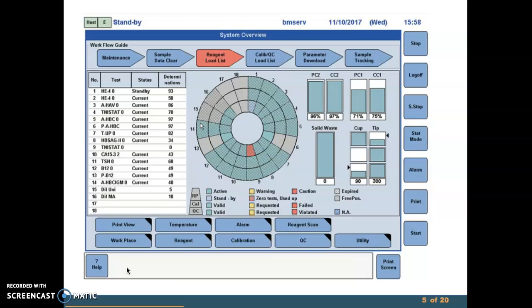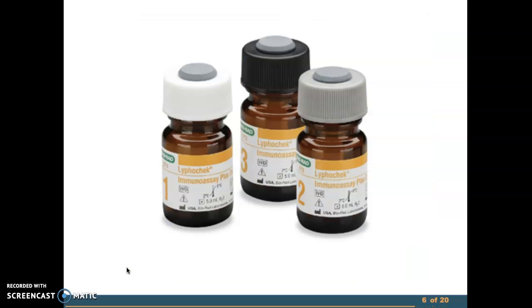On this diagram, you can see that each reagent pack has a tab on the middle circle that corresponds to where it is on the reagent rotor in the middle of the machine. If you select the tab corresponding to each reagent, it will tell you when the next calibration is due. Further, quality control assays need to be run each morning on every reagent pack on the machine before testing patient samples. Once the results for this quality control are finished and print off, they need to be entered to the database that evaluates whether they are in range or not.